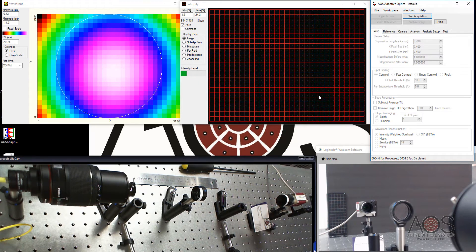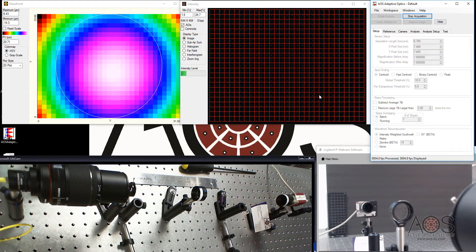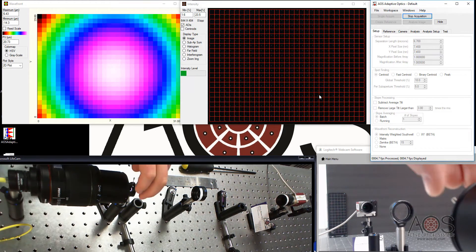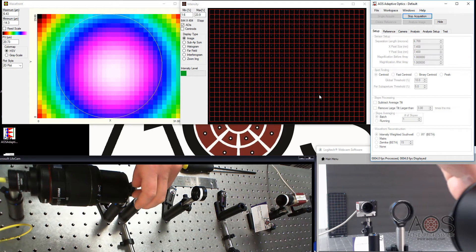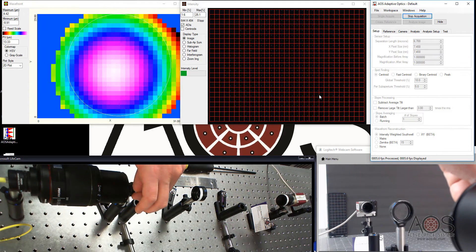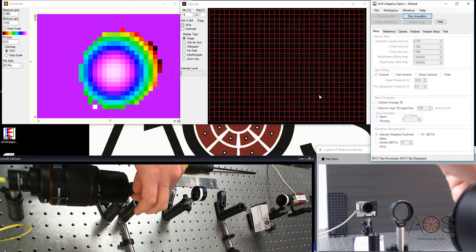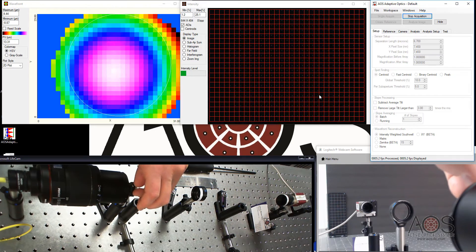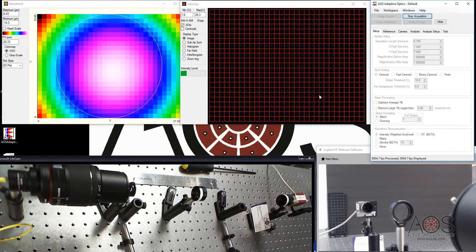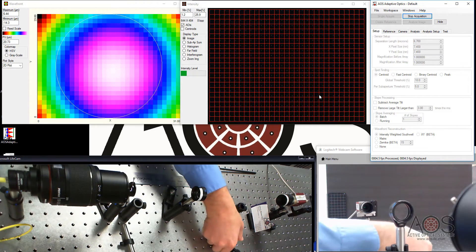As I showed in the last video, it's easier to see in this slope plot. There's that massive diverging wavefront, and you can see I'm exceeding that dynamic range quite considerably. Bring that out. But I can also use this for centration. If I've done this all right, I can close this iris. I'm pretty close to center. Not perfect, but pretty close to center here. Good enough for this demonstration today.